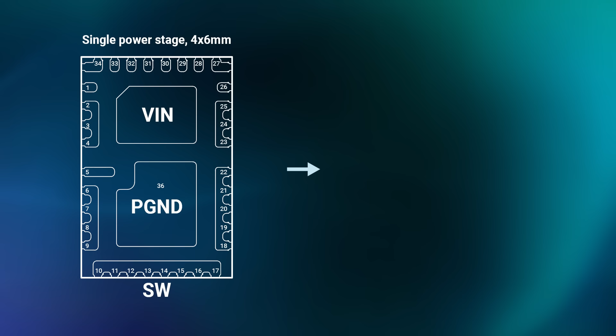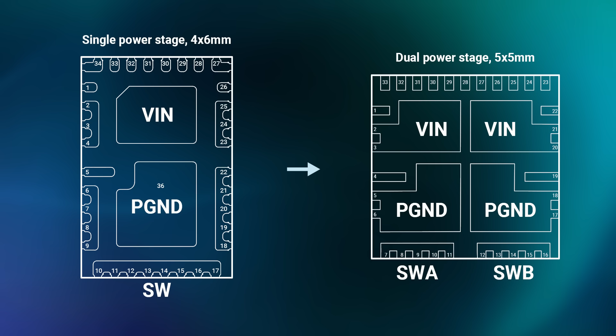One trend that we are seeing in the market is a move from a single-phase power stage to a dual-phase power stage. This helps to pack more current into a smaller space, and that helps to address the current density challenge. Now, TI's dual-phase power stage enables 100 amps per phase peak current, which really helps to address the high peak currents seen in these AI processor applications.